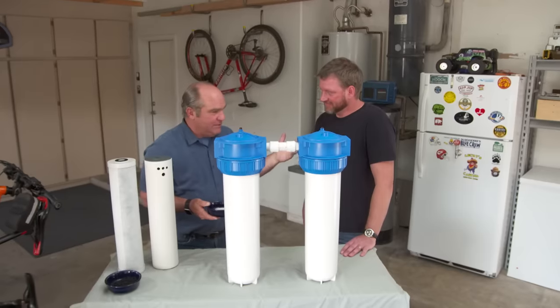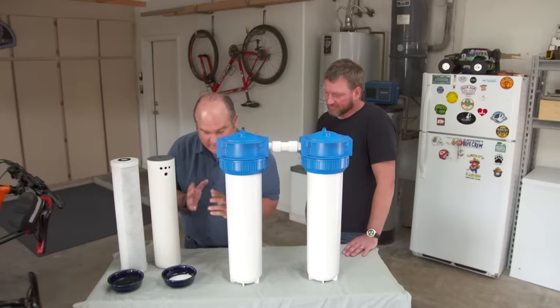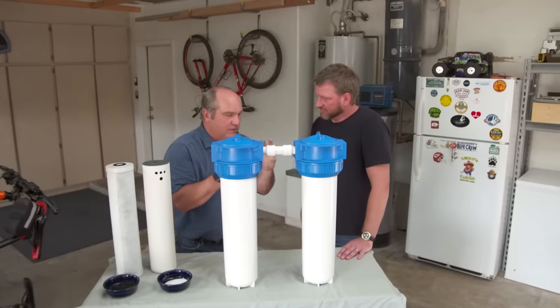I'm going to eat this? You are, right now. Wow, that is sour. Tastes like my kids' candy. Absolutely. So this is actually a food-grade material that's used in kids' candy and many different uses in the food industry. But what it gives water is a very unique characteristic. Unlike the resin that attracts the magnesium and the calcium and then you have to discharge it to a drain, what citric acid does is it encapsulates the magnesium and the calcium and keeps it in the water solution moving through, and doesn't let it bond onto the pipes.